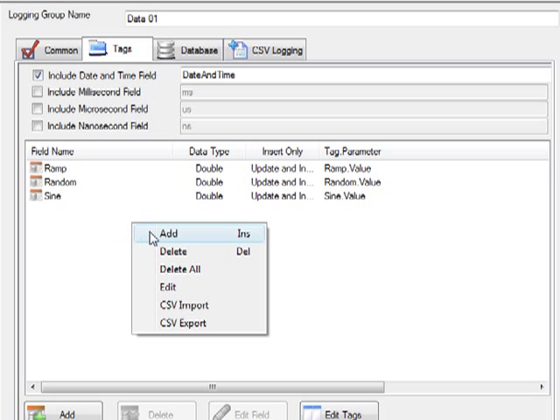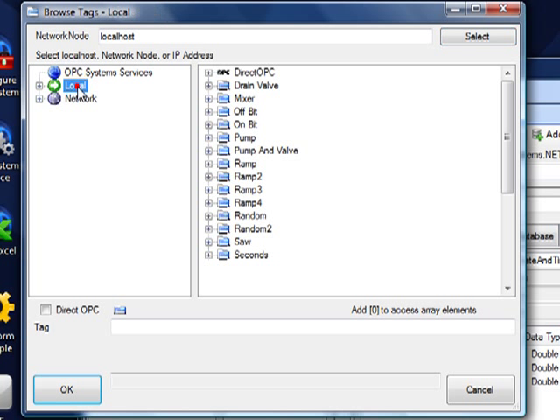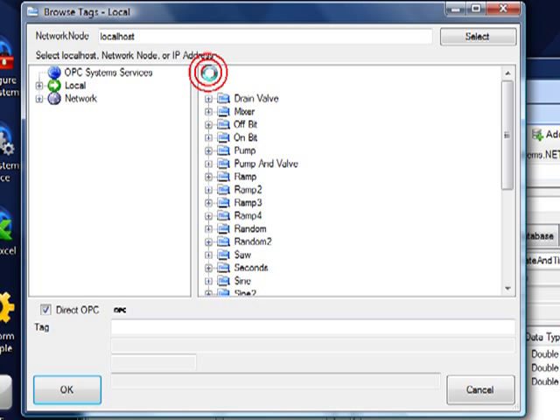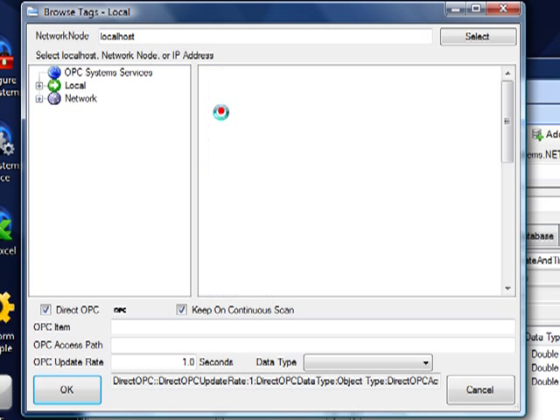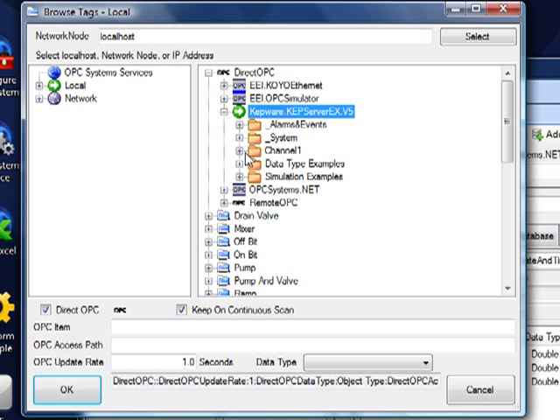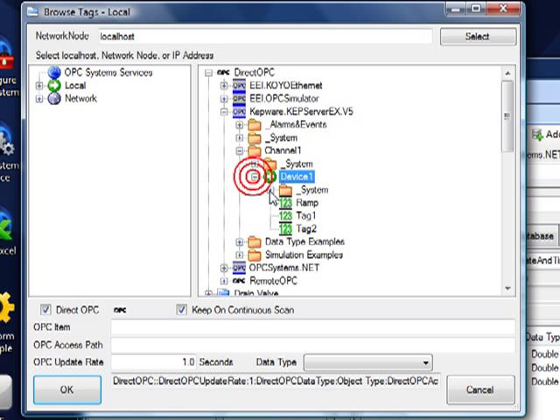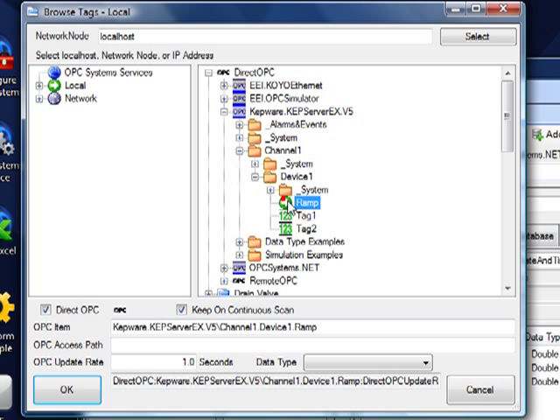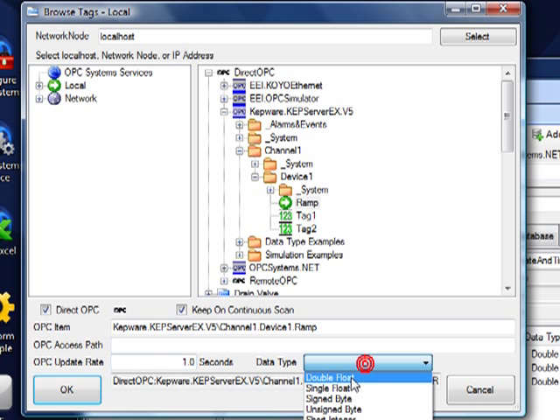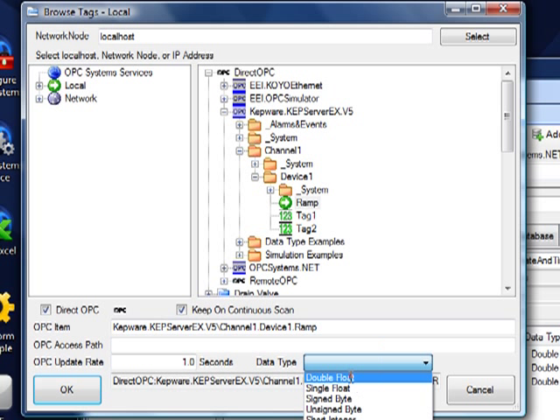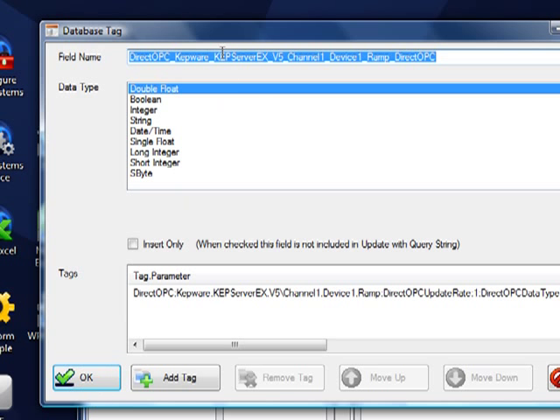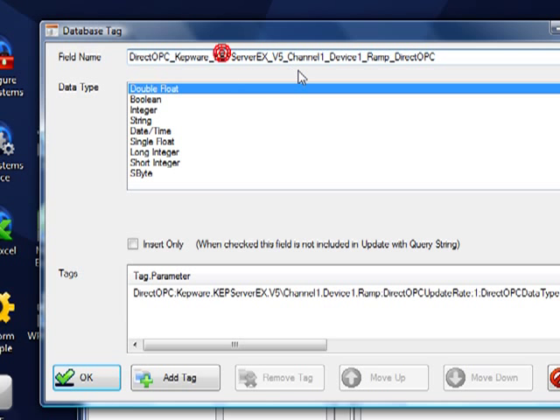If you wanted to connect directly to OPC servers without using the OPC Systems.NET tags, you can do that also with the direct OPC interface at the top. Here we can browse an OPC server for a particular item and add that to the configuration. We can also specify the update rate that we want to subscribe to and the data type that we're going to log for that item. We'll click OK. And I'm going to shorten up this field name. And we'll click OK.